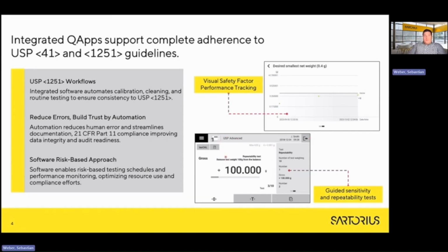This screen below shows a QApp workflow. The user is guided directly on the screen to perform the repeatability test in this case. But this USP Advanced QApp also contains all the other needed tests, and it will guide the user directly, and the results will be evaluated and also recorded. And for the recording, we have also a nice feature here. This is visual safety factor performance tracking.